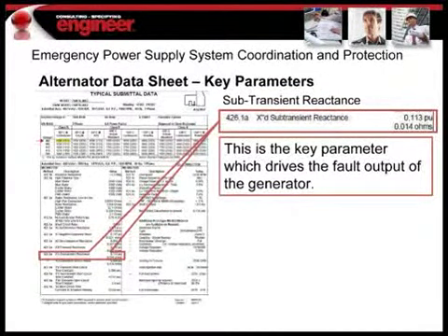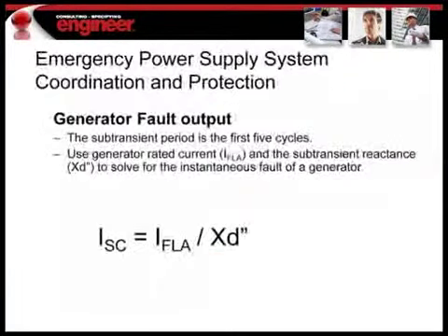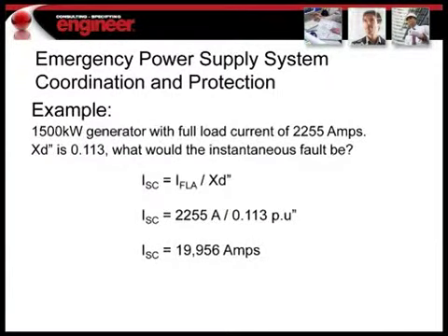It's a scary word, I know, but it really is a pretty simple concept. Subtransient reactance is basically if you take the full load amps of the generator and divide it by the subtransient reactance, you get what the fault output of that generator is. It's a very basic equation with a scary word, but it's pretty straightforward. So if we take an example for this unit that we're looking at, a 1500 kW generator at 2255, and you remember that our XD double prime was 0.113 on the alternator data sheet, that gives me a fault output of almost 20,000 amps.